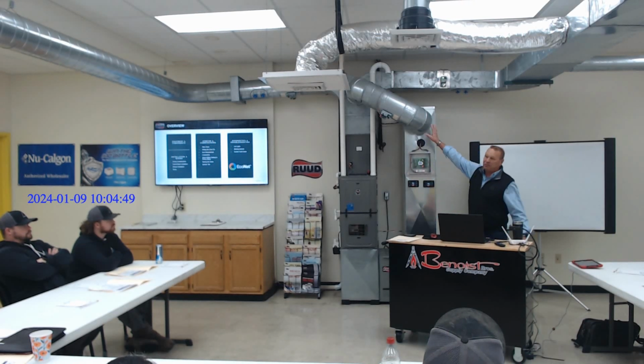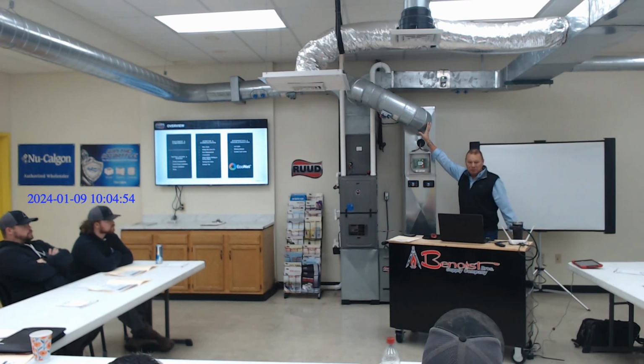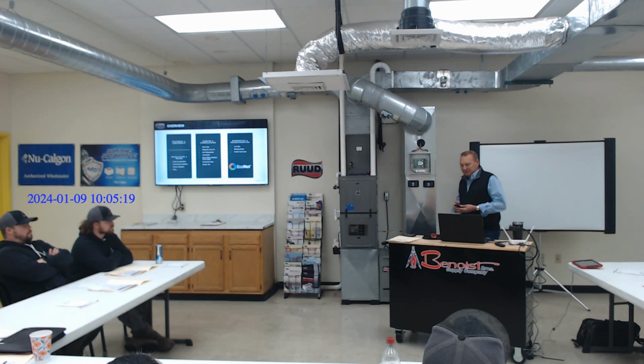And this is the other place we're running into problems with zoning. We're not thinking about that out of the box because we think we put a bypass in and we've solved all our issues, right? I can dump that air. Now I've got options, which we'll go through. I can make a dump zone somewhere. I can maybe do leakage or over-conditioning of the first zone and create leakage. But that's not ideal, because then your whole zoning is defeated, right? If I can't keep the temperatures where I want them in each zone, okay? So that's where we've got to start thinking out of the box.